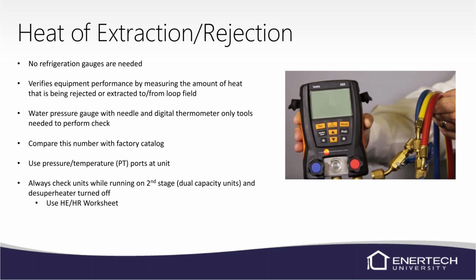You'll need a digital thermometer. You can use an analog, I guess, a little dial, but I would recommend a digital. We have a Cooper thermometer that we sell as well. I'm not trying to just promote our products. It's because I found these things and then we started to sell them. We didn't sell them before I got them. This Cooper has a tapered end on it, so it'll slide into those PT ports a lot easier. We used to give away a thermometer when you come to our trainings, and you'd put it in that PT port, go to pull it back out, and the head and the wires would come out, and the metal shaft would stay in the PT port. So you'd have to grab your channel locks and pull it out and pinch it and everything else. So we don't hand those out anymore. Again, that's a Cooper thermometer and a Dwyer digital pressure gauge.